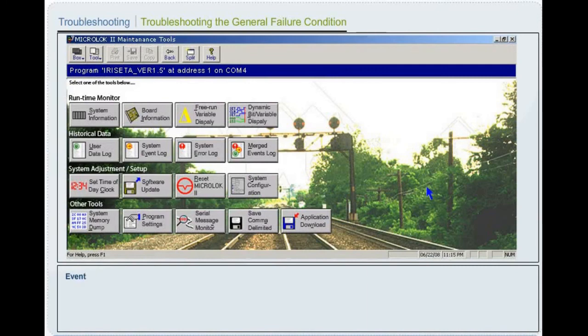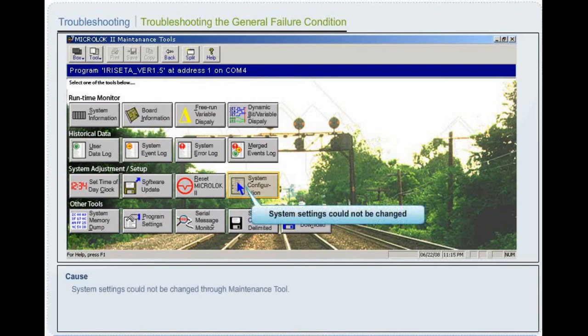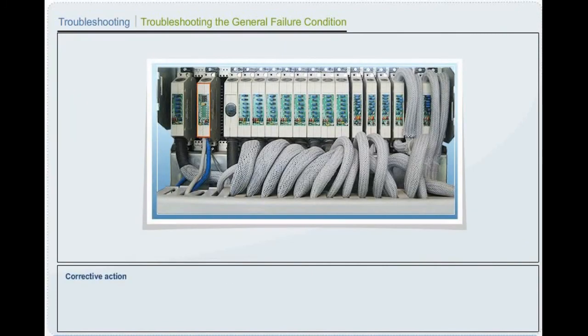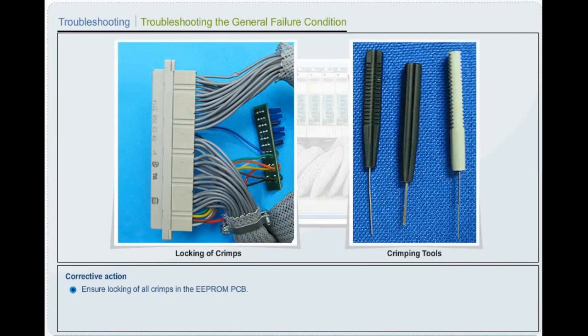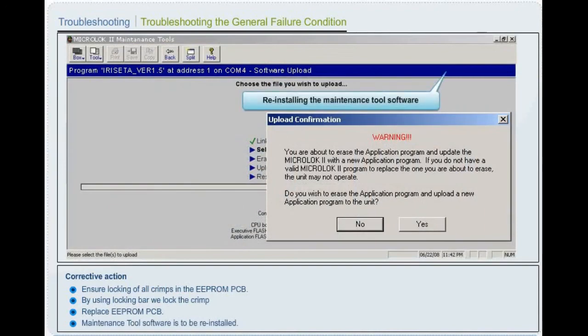Troubleshooting. Troubleshooting the general failure condition. Event: System configuration mode failed. Cause: System settings could not be changed through maintenance tool. Corrective action: Ensure locking of all crimps in the electrically erasable programmable read-only memory PCB. Replace EEPROM PCB. Maintenance tool software is to be reinstalled.